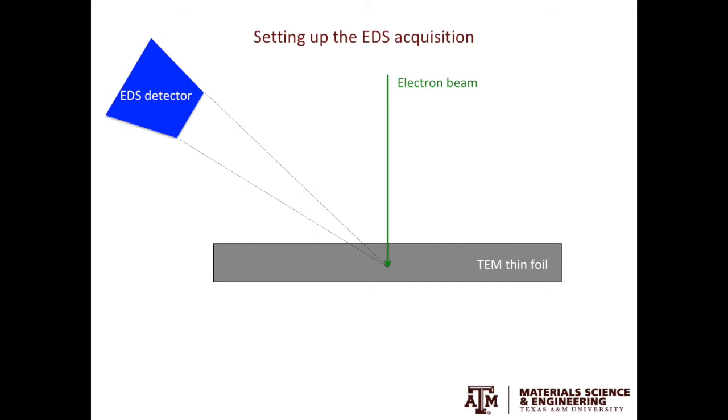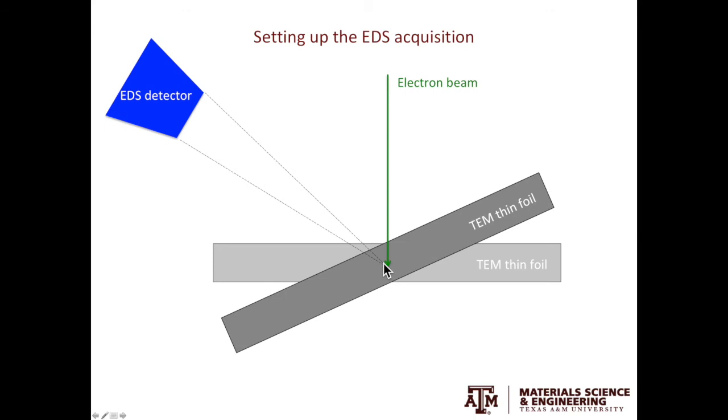Here, we'll explain why. Let's look at the specimen with 0 degree tilt. We have the incident electron beam hitting the specimen, generating X-ray, and this is the absorption distance. Now, tilt the specimen towards the detector. And this is the new absorption distance, which is shorter than the previous case.